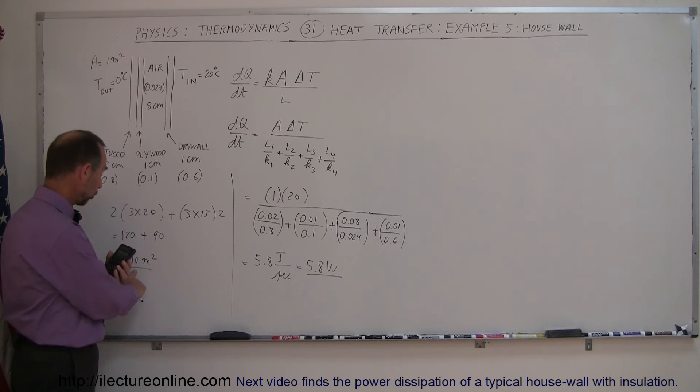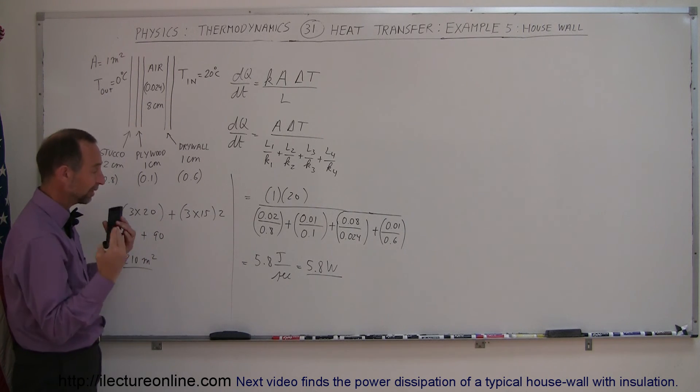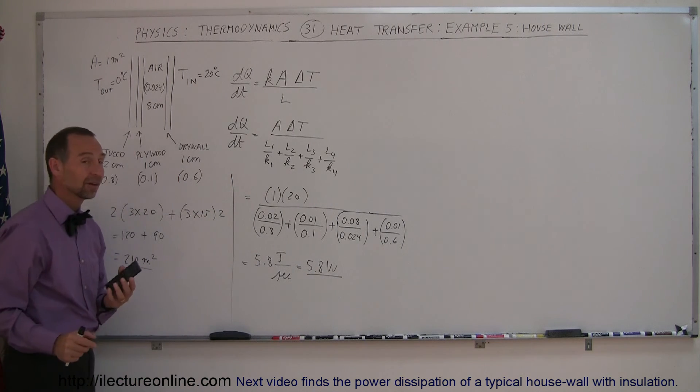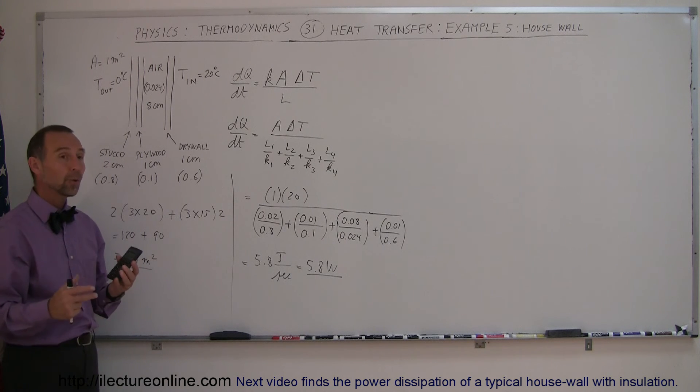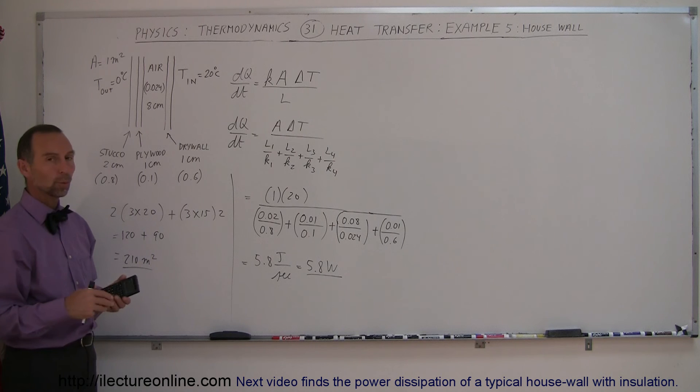All right, so if we multiply the total area of the house, that's not including the roof, not including the floor, simply the walls, 210 square meters times about 6 watts per square meter, 6 times that, that would be 1,200 watts of heat being lost to the walls on a cool winter day.